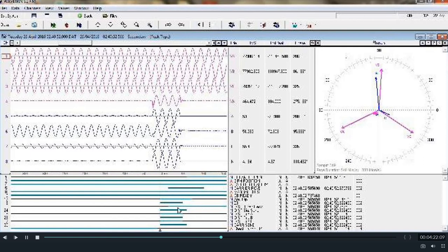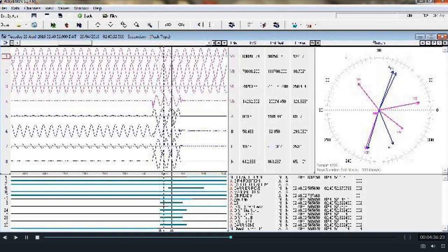These lines indicate the digital channels or the status, which gives us an idea of the fault or what has happened during the fault or the opening of the circuit breaker. Just above these digital channels you will be able to find the time stampings. When the relay started sensing the fault or when the relay triggered, that time is stamped as the 0th time.